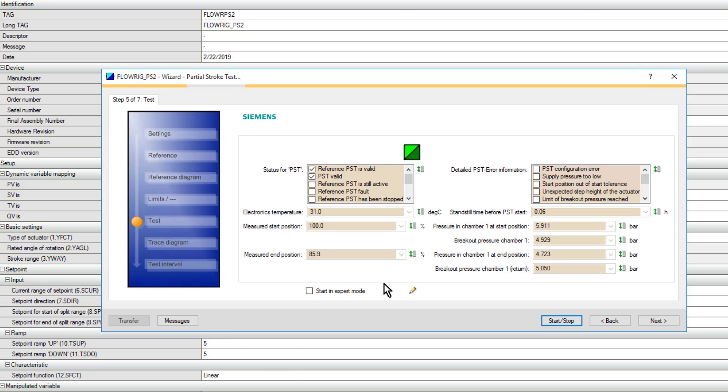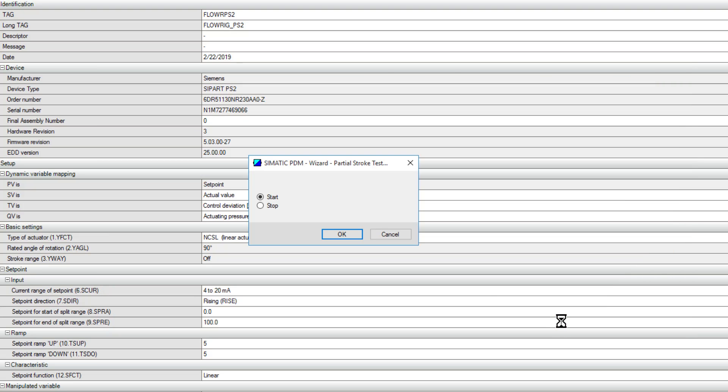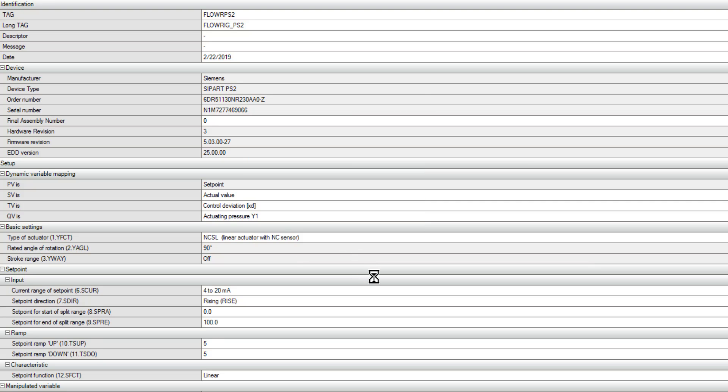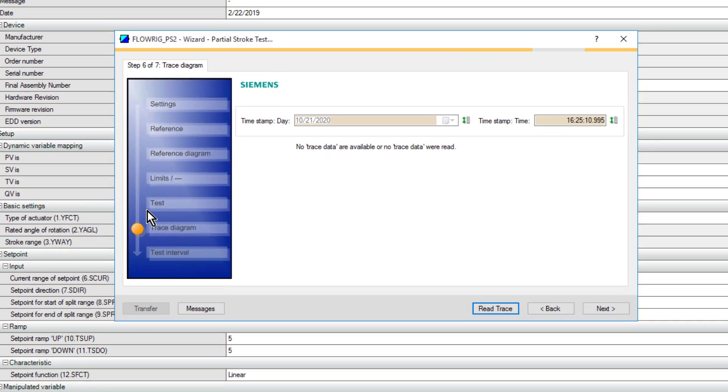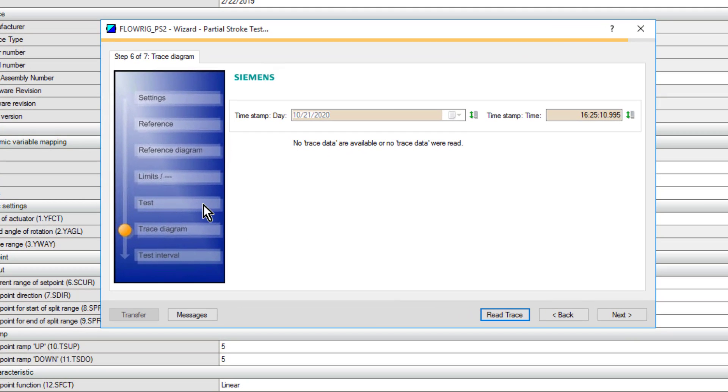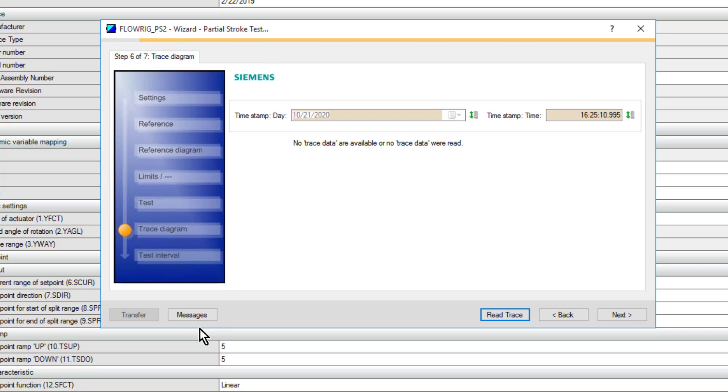The process is the same - I can start in expert mode, but if I click start stop, it will perform my latest partial stroke test. When I've finished my latest partial stroke test, I can go and look at the trace diagram if I want, but there's a better way to do that. If we move on to the next stage.